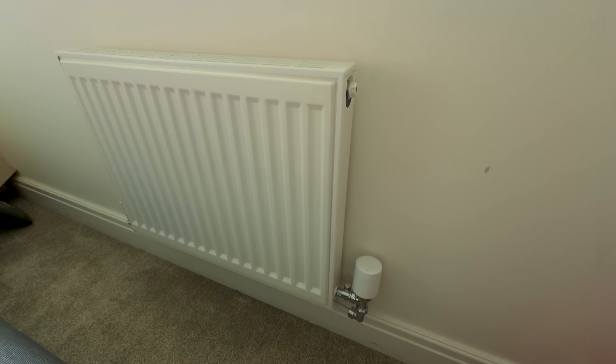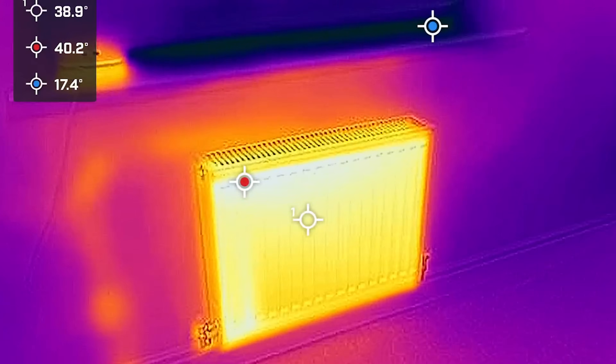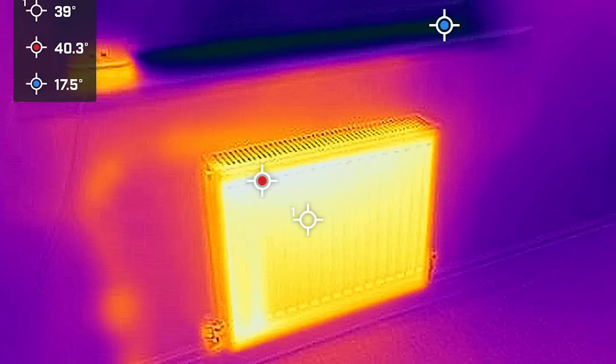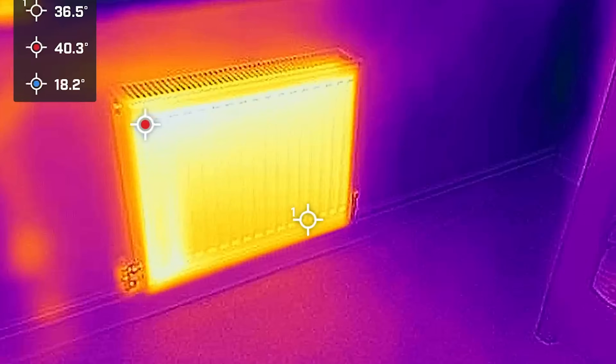Can we just get the firmware to reverse this so it throws cold water into the house? One of the main technical issues is that a radiator is a radiator — it's meant to radiate heat. Hot water comes in one side, hot water rises, cold air gets sucked through the bottom, creating convection that warms the room. The cold water returns through the bottom pipes. The problem with cold water going through a radiator is that the cold water stays at the bottom — the convection effect simply doesn't work the same way.